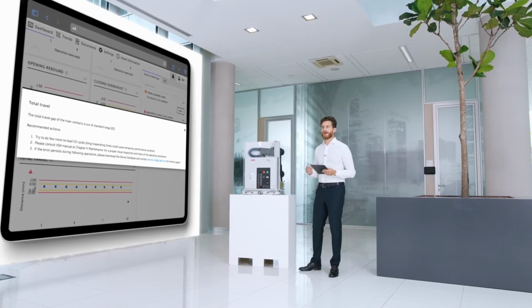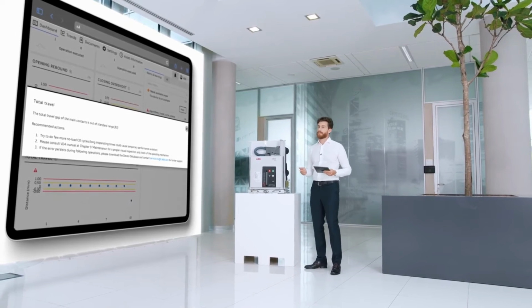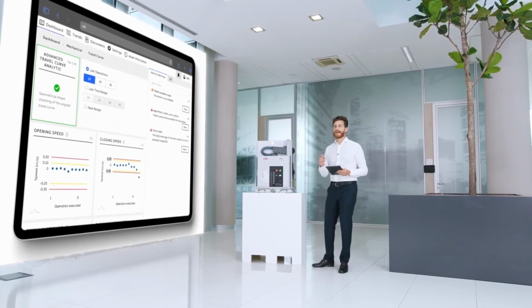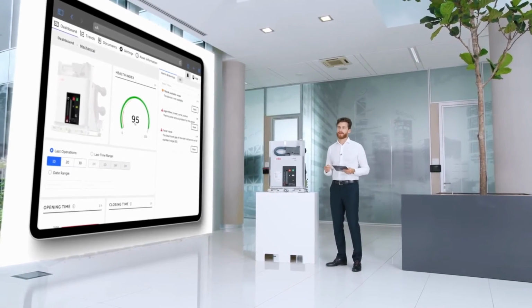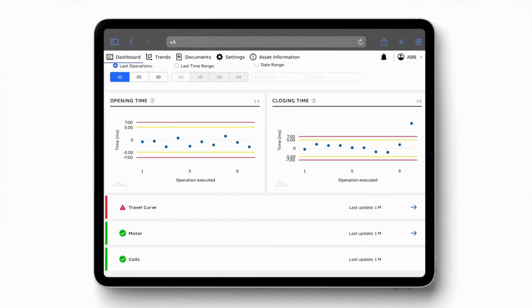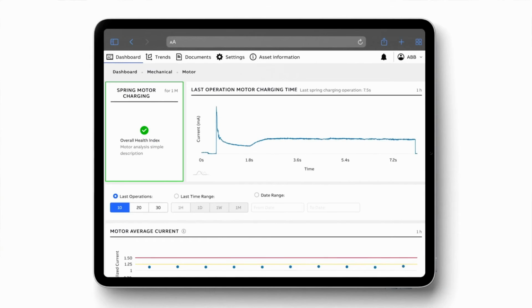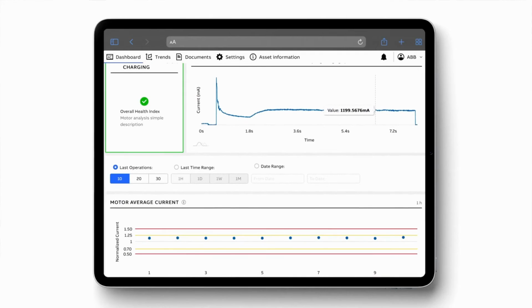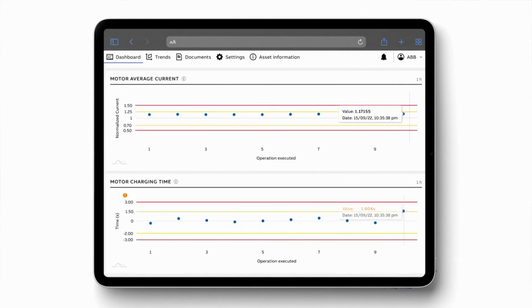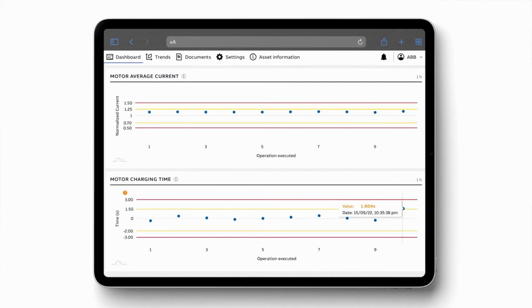The accessories are also monitored. For example, the charging motor device can be influenced by operating conditions over the years and display signs of wear. Therefore, we monitor current absorption profile and advise on a simple accessory replacement before it's too late and worse damage is done to the equipment.